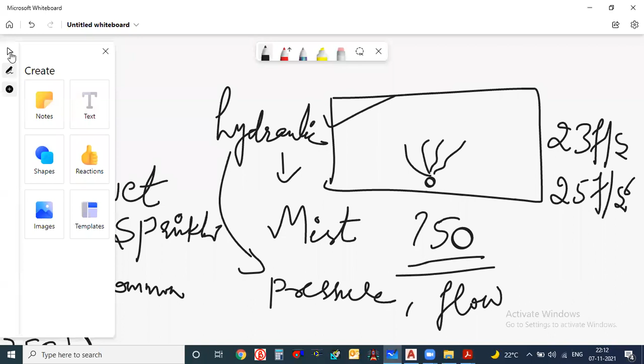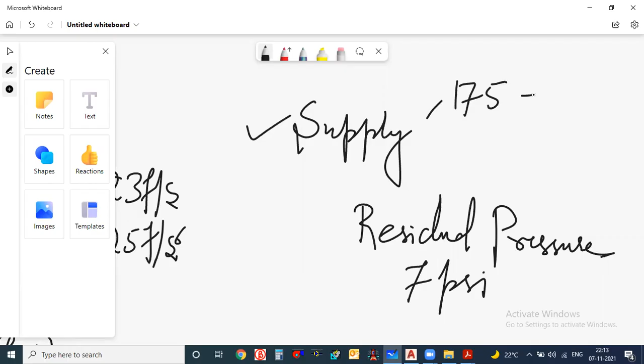Why? Because in demand mode, we require the residual pressure. But here they have not mentioned anything about the residual pressure. Just remember this thing. Like in NFPA 13, they have given the residual pressure, like 7 psi. But here in the mist system, we don't find this residual pressure. So instead of going with demand mode, we can go with the supply mode, where we can write any suitable pressure range from 175 psi to 500 psi, depending upon the type of the building and the type of the pressure requirement.